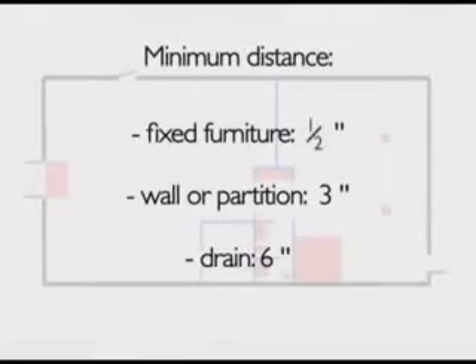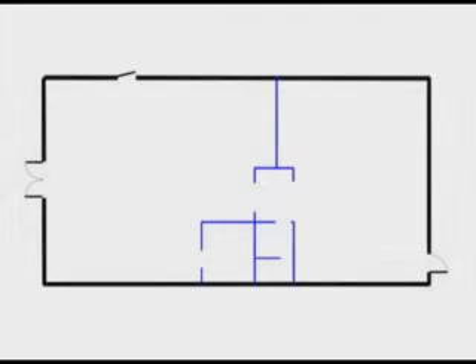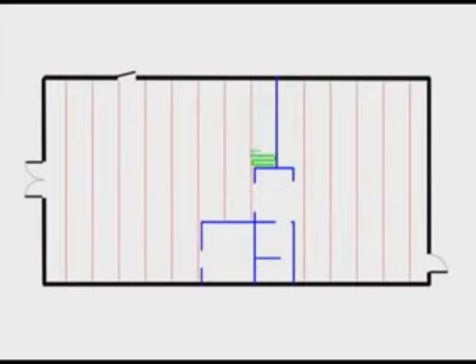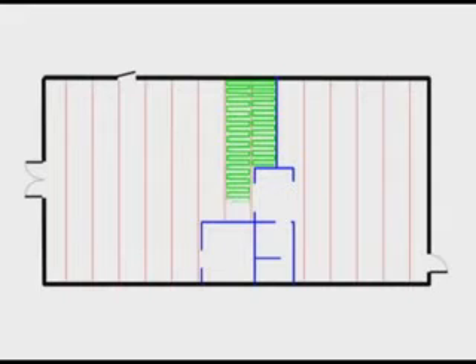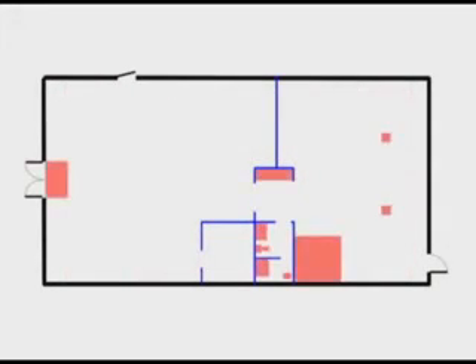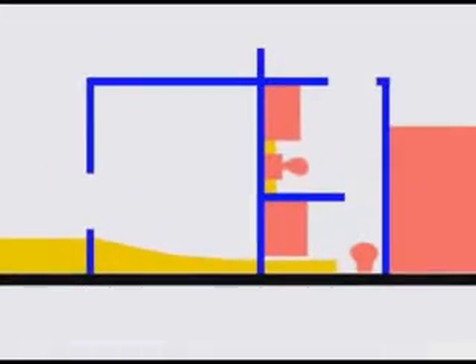When designing the installation, you must respect the minimum specified distance between the cable and an obstacle. A cable cannot be placed less than ½ inch from any fixed furniture, 3 inches from any wall or partition, and 6 inches from any drain. When planning the installation, keep in mind that no single pass of cable can exceed 10 feet. If the room requires a greater length, divide it into sections. You must leave a buffer zone that will be readily accessible at the end of the process, where you can place any excess cable if necessary. Select low traffic areas, such as behind a toilet or a door.